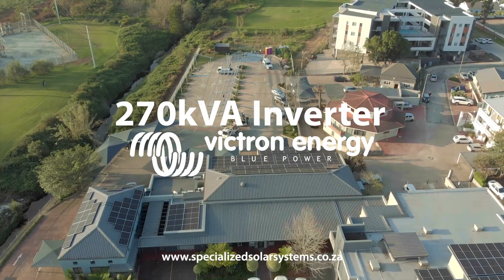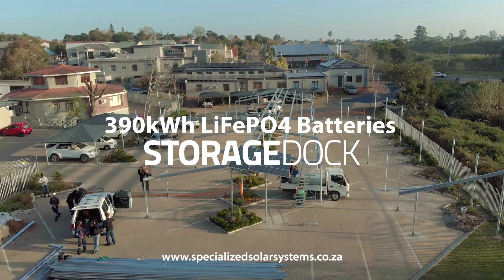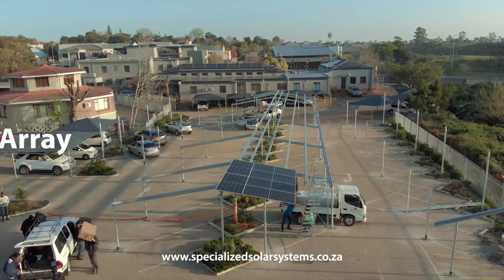The installation consists of a 270 kVA Victron inverter, a total battery storage of 390 kWh, and a PV array consisting of 600 solar panels, giving us a total of 330 kW peak. The PV array is split between rooftop solar and carport structures, designed and manufactured in-house by Specialized Solar Systems.